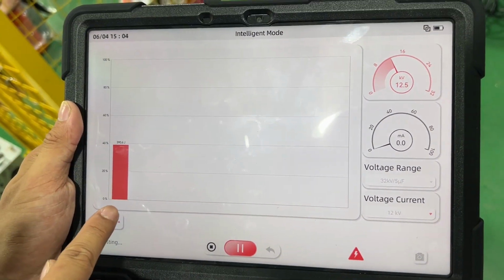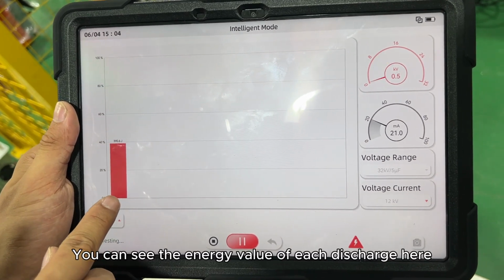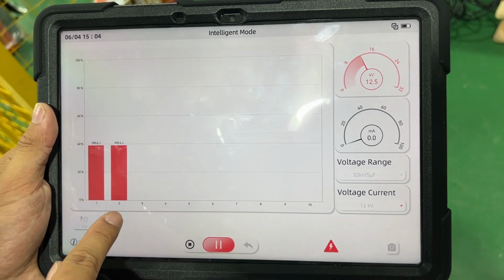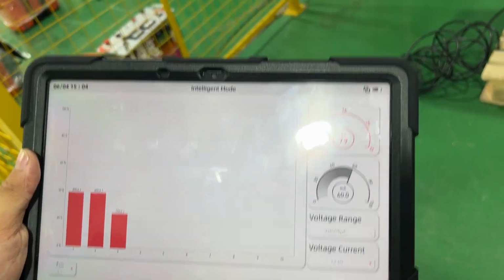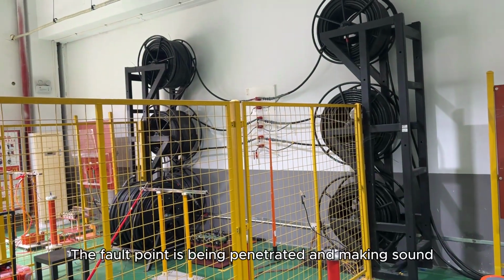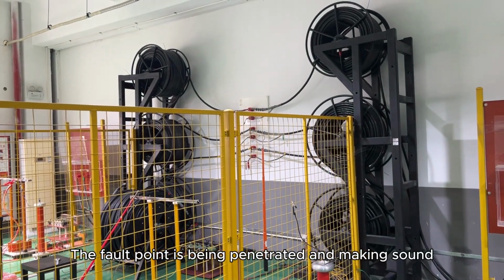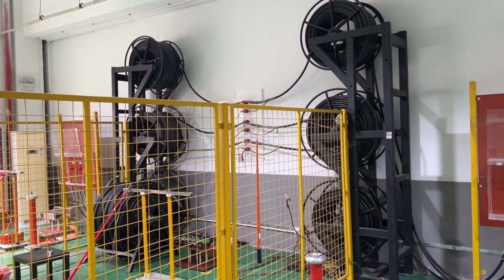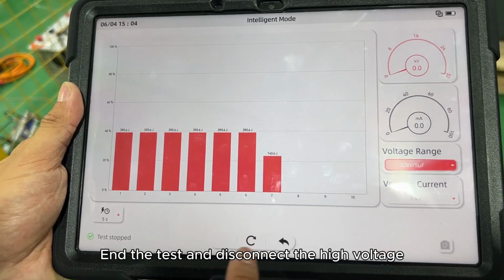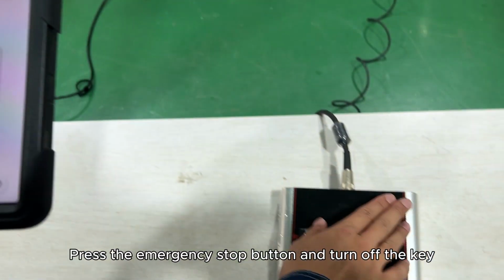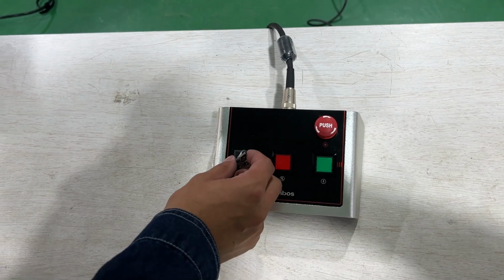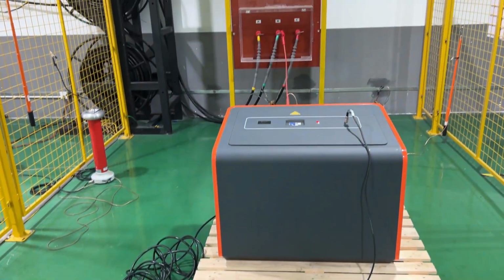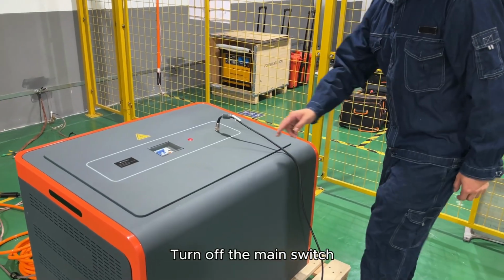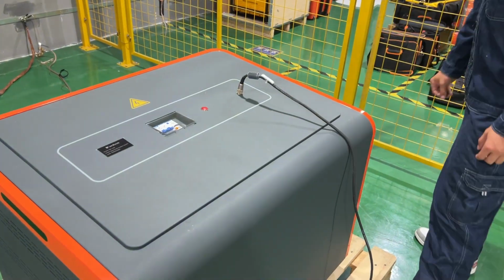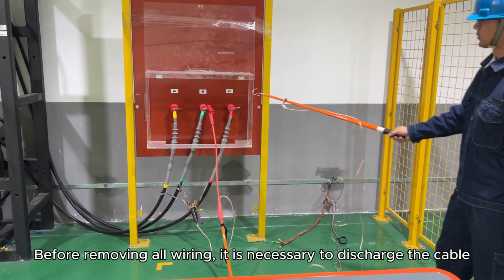Similarly, set the voltage. You can see the energy value of each discharge here. The fault point is being penetrated and making sound. End the test and disconnect the high voltage. Press the emergency stop button and turn off the key. Turn off the main switch. Before removing all wiring, it is necessary to discharge the cable.